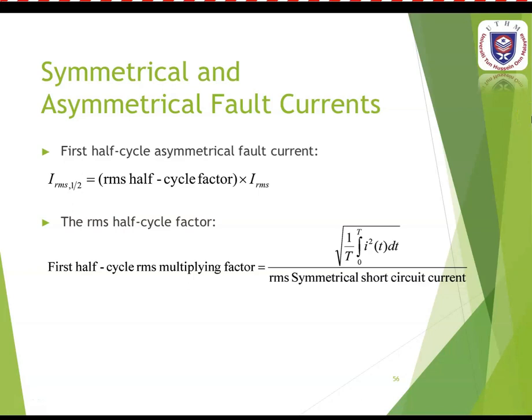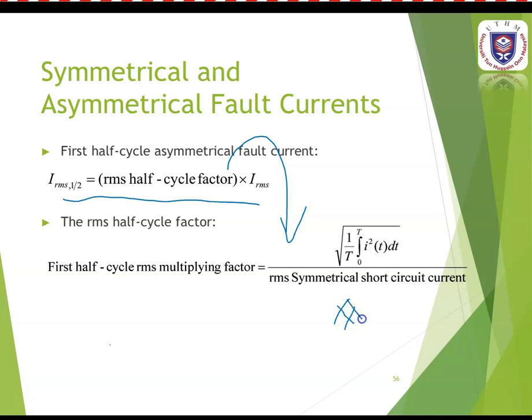For this analysis, we also need the first half-cycle asymmetrical fault current, calculated as: I-half-cycle = RMS half-cycle factor times IRMS. This half-cycle factor is obtained from the asymmetrical current factor table.